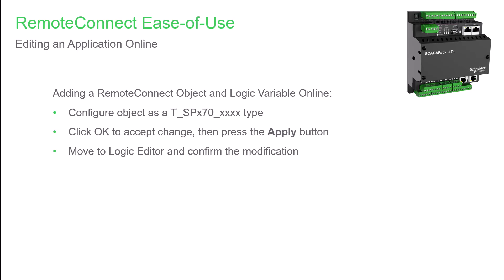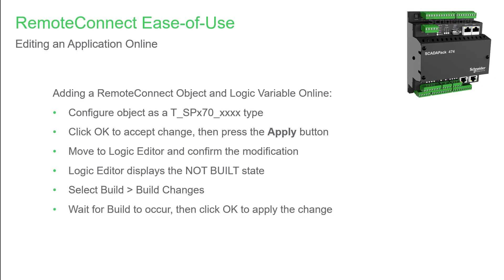Next, move to Logic Editor and confirm the modification. You'll see that the Logic Editor status bar now shows 'not built'. Now in the build menu, select build changes. This option needs to be used so that the edit doesn't cause an offline state. When prompted, click OK to apply the modification. And finally, you can go to the derived variables folder to verify that the new variable exists.